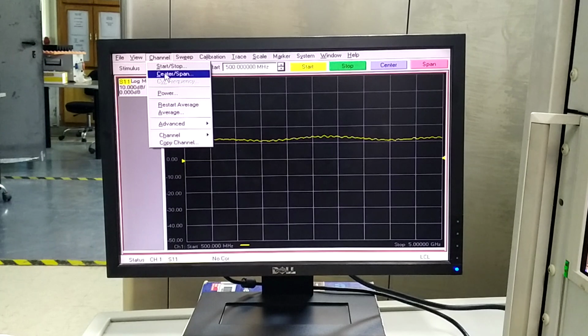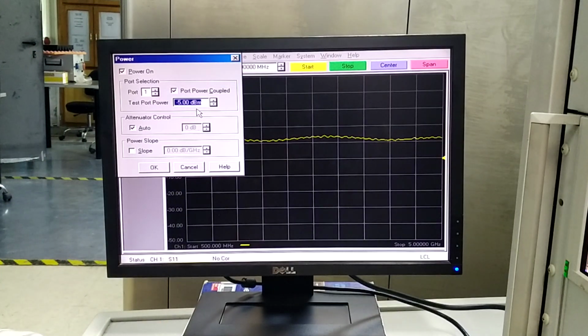Now there's another option of center and span. You can also use this option to enter the center frequency and a span if you would like to enter the frequency like this. There's an option of power. If you go into the power option, this shows you how much test port power the VNA is generating to the particular test port that, at the end of the day, goes to the DUT. This power is set by default to minus 5 dBm, so we keep this as such.